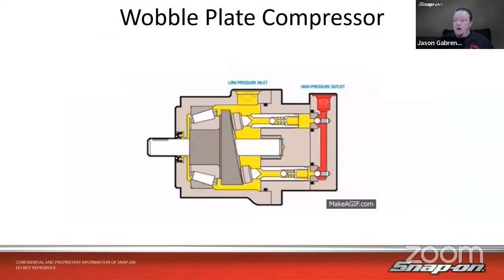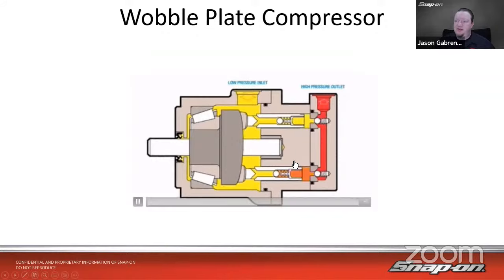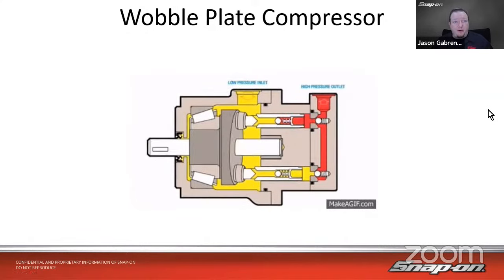There's also a wobble plate compressor, which does pretty much the same thing, except the plate itself is cut on an angle, so that one's not variable. It just spins around. We get the low pressure coming in, with some check balls that allow the low pressure in, and then it turns to high pressure, which overcomes the spring pressure and is able to go out that way as well.